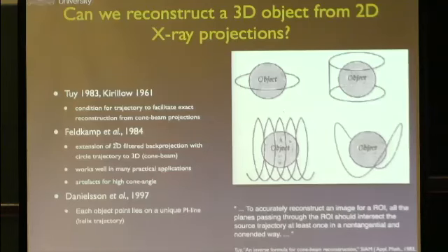Nevertheless, in '84, Feldkamp et al. came up with a very nice generalization of the 2-dimensional filtered back projection into 3D cone beam for exactly this trajectory. And indeed, it's been very successful, and in micro CT it's almost been exclusively used, both because it's efficient to compute and it's very, very stable.